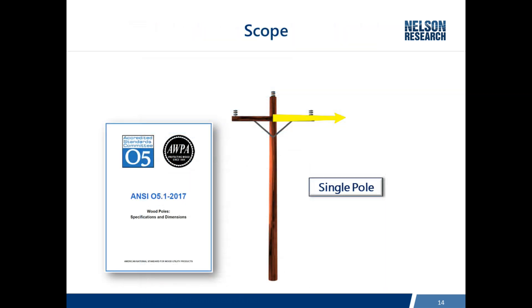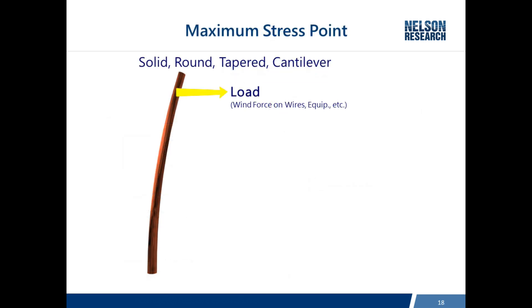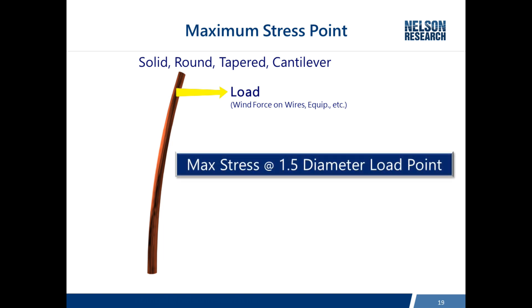The standard most often used is ANSI O5.1. In the scope, it clearly lays out that this standard addresses single poles in a simple cantilever installation — fixed at the ground line and bending at the top. It also addresses only transverse loading, which is wind loads blowing on the wires and trying to blow the poles over sideways. All of the strengths in this standard are specified at the ground line. When you have a pole that is solid, round, and tapered in a cantilever installation, the maximum stress point — where you expect a pole to break — is where the diameter of the pole is one and a half times the diameter at the load point.